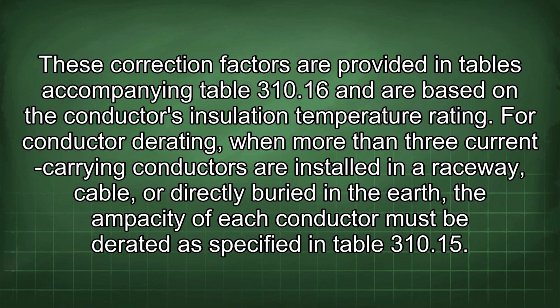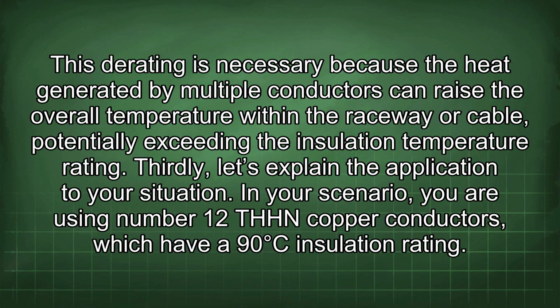For conductor derating, when more than 3 current-carrying conductors are installed in a raceway, cable, or directly buried in the earth, the ampacity of each conductor must be derated as specified in Table 310.15. This derating is necessary because the heat generated by multiple conductors can raise the overall temperature within the raceway or cable, potentially exceeding the insulation temperature rating.